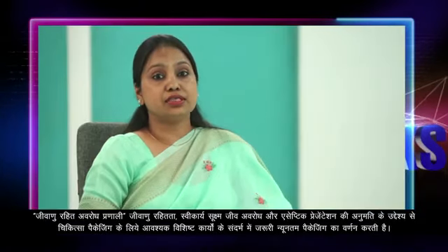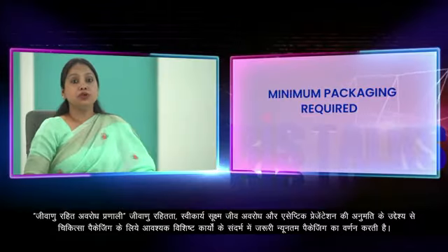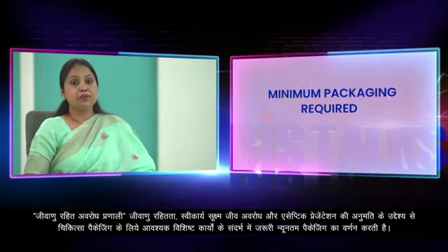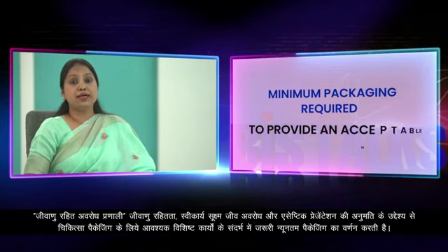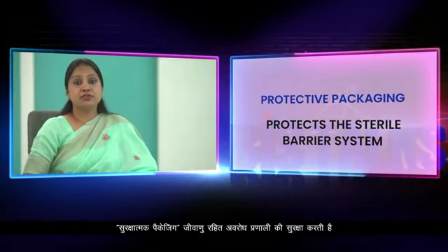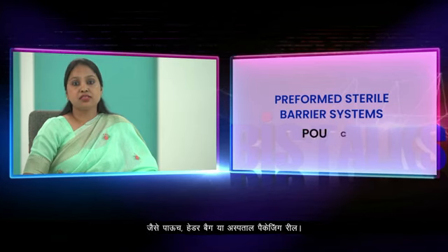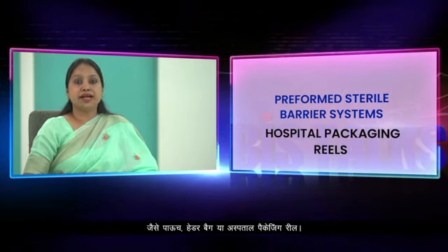The sterile barrier system describes the minimum packaging required to perform the unique functions required of medical packaging to allow sterilization, to provide an acceptable microbial barrier, and to allow for aseptic presentation. It is essential to ensure the safety of terminally sterile medical devices. Regulatory authorities recognize the critical nature of sterile barrier systems by considering them as an accessory or a component of a medical device. Protective packaging protects the sterile barrier system, and together they form the packaging system. And preformed sterile barrier systems such as pouches, header bags, or hospital packaging reels.